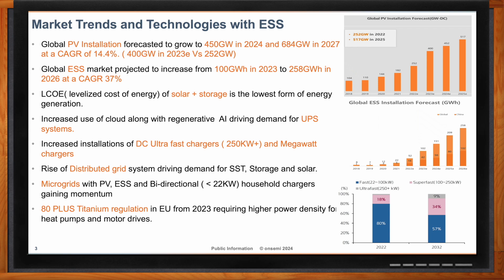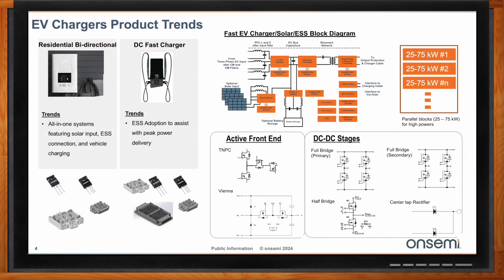We have two types of EV charging. One is level 2 chargers, which are normally located at homes in residential locations. They are direct AC chargers mostly, and they are up to 11 kilowatt in general, but can go up to 19 kilowatt. These level 2 chargers are mostly AC connectors with GFCI circuit breakers for safety purposes. With new level 2 chargers, residential solar-based direct DC charging is also being included as part of the storage and EV charging capability.